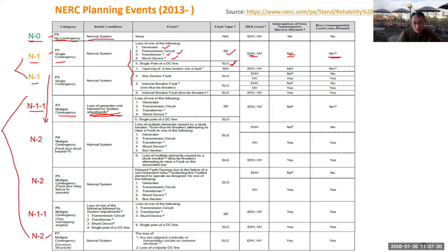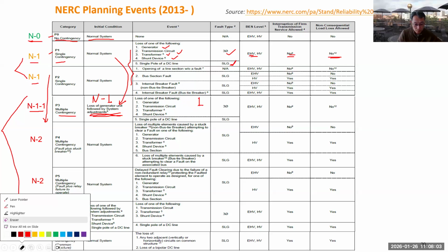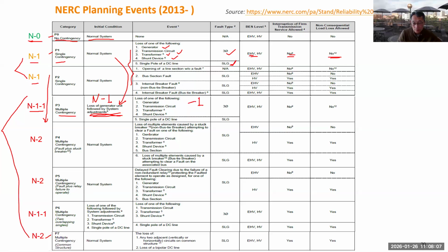This is based on assuming you're already at the initial system condition where you've already lost one element — that could be from P1. So it's a condition from P1, and then you add another contingency. That's why this is called N minus 1 minus 1. The initial condition is already N minus 1, so instead of using positive 1, I need to use minus 1. The base condition is you've lost one component, and then you have another single contingency.